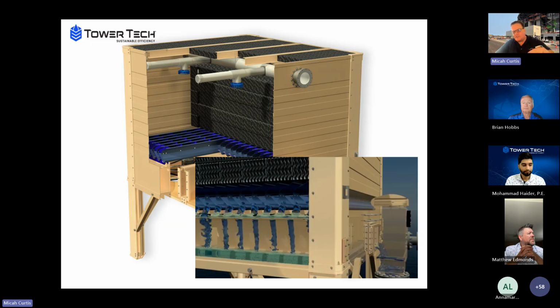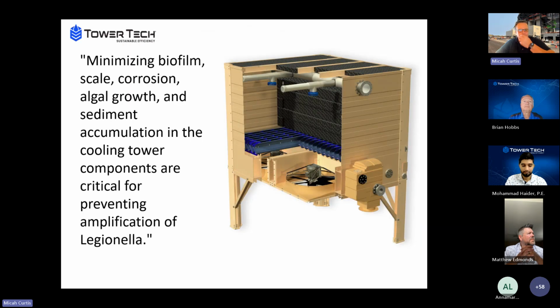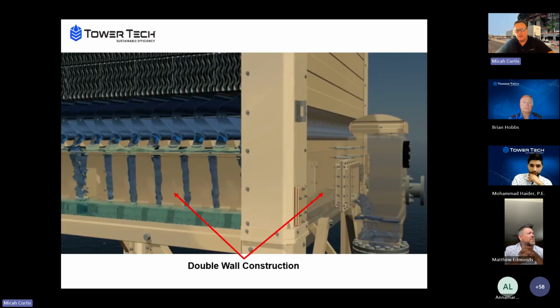The water actually moves and exits the tower at a high velocity, 5 to 7 feet per second, so there's no sediment buildup. The sediments are held in suspension in the water. The chemicals mix greatly and easily, and it definitely minimizes Legionella risk because of that. The Tower Tech tower does not have any corrosive components. It's all pultruded FRP and stainless steel bolts. No galvanized steel whatsoever. No dissimilar metals. Totally non-corrosive. So here's another shot of the flow-through basin.